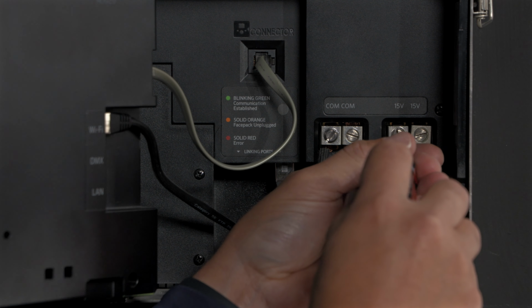You can scroll over and see the other chassis that are associated with the system, and make sure that they're not overloaded. To double check, press Home to return to the home screen, then use both the Home and Return buttons to go back to the diagnostic screen. Scroll through the system loads. We see no system overloads. Press Home. And now we have verified that the field short is fixed.